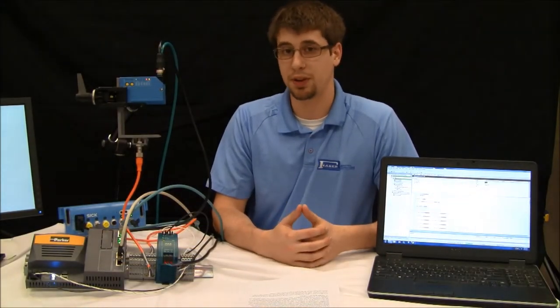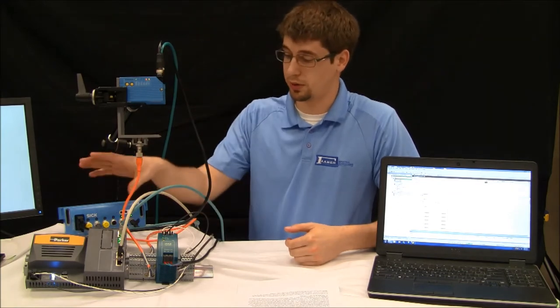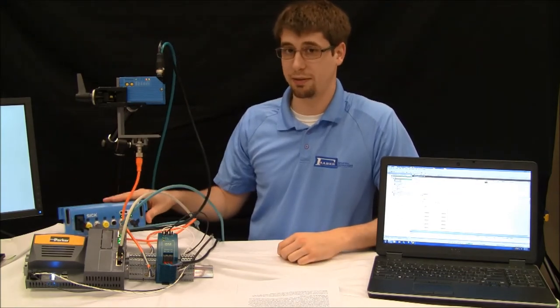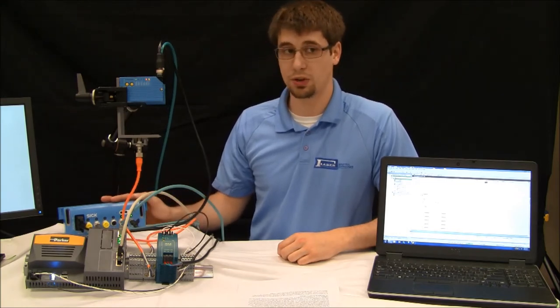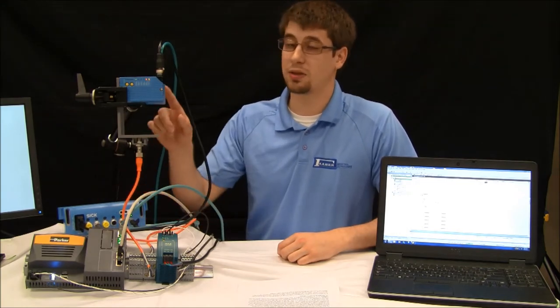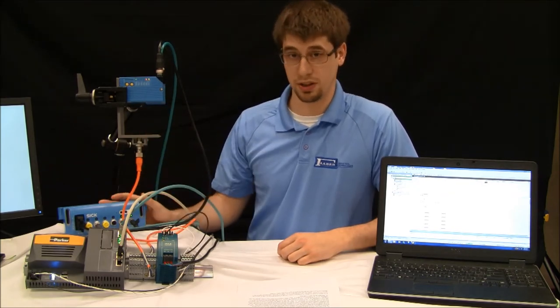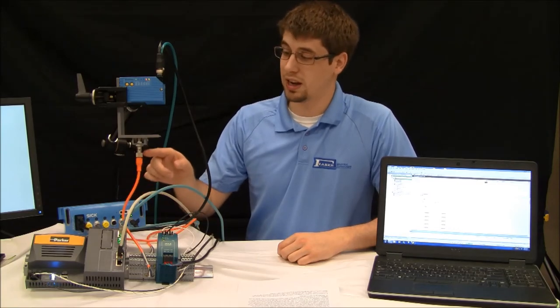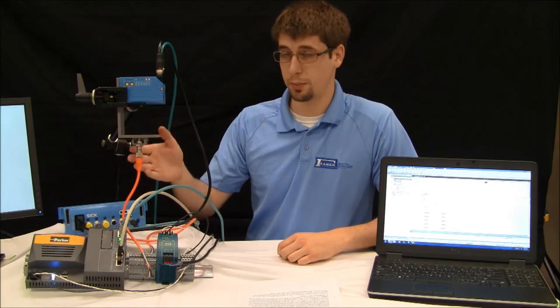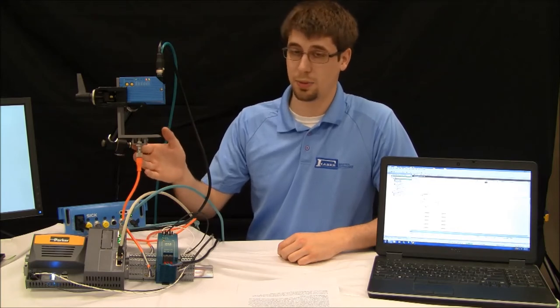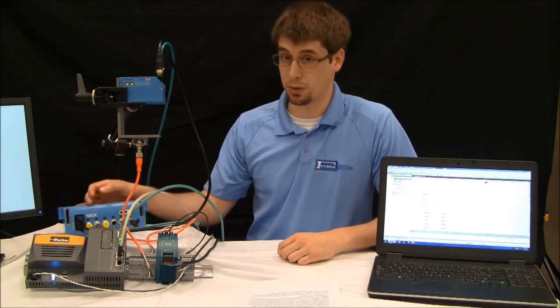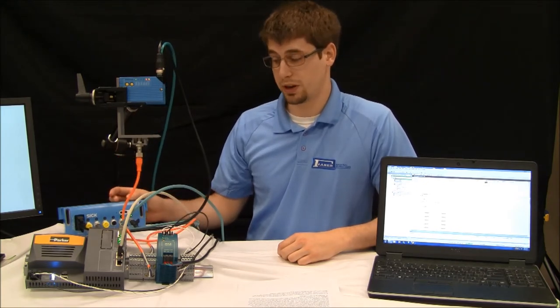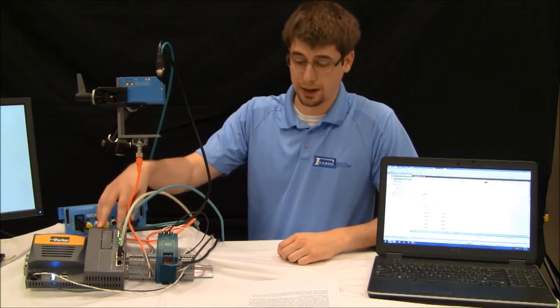The first step that must be done is properly setting up the scanner. In order for the scanner that we've chosen to work properly with the PAC, it requires us to use a CDF600-0300, which is a field bus module from SICK that allows the CLV600 series barcode scanners to work properly in EtherCAT network. We will also be using a magnetic proximity sensor to trigger the barcode scanner. Both the barcode scanner and the magnetic proximity sensor will need to be wired into the EtherCAT module using the proper cables. And then the field bus module will in turn need to be wired into connector X1 on the PAC.